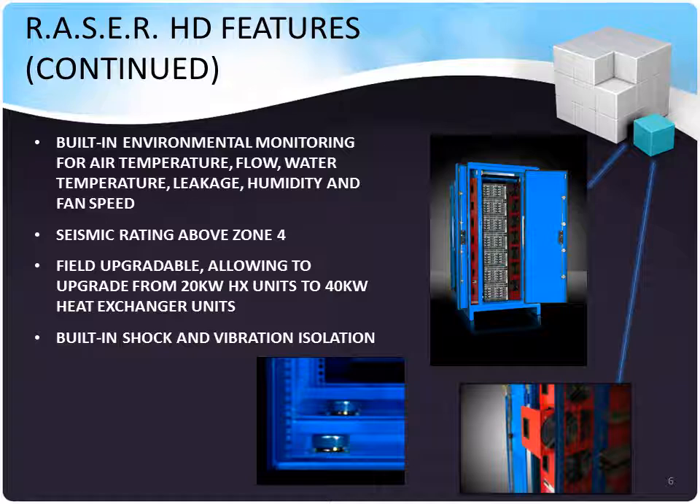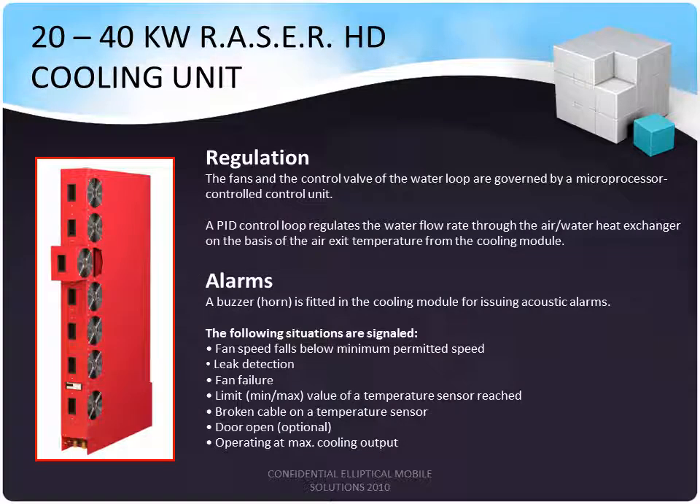Built-in shock and vibration isolation protects the equipment so that you can have supply chain advantages, such as having the operating system and equipment burned in and configured, then having the unit transported with everything in place. The R.A.S.E.R. cooling units are highly sophisticated and contain quite a few sensors. They are regulated with microprocessor-controlled units. The PID control loop regulates the water flow through the air-and-water heat exchanger on the basis of air exit temperature from the cooling module, making them self-regulating.